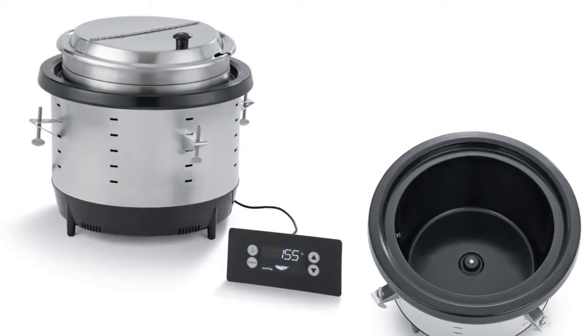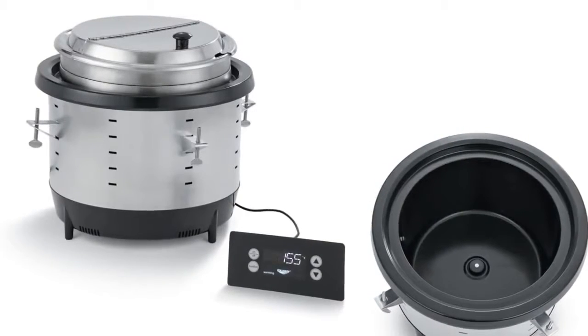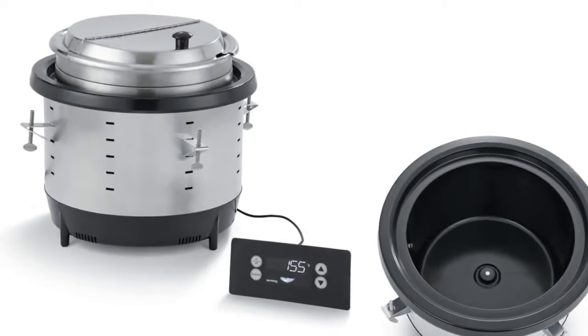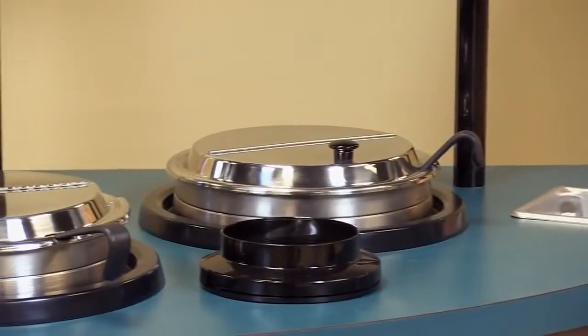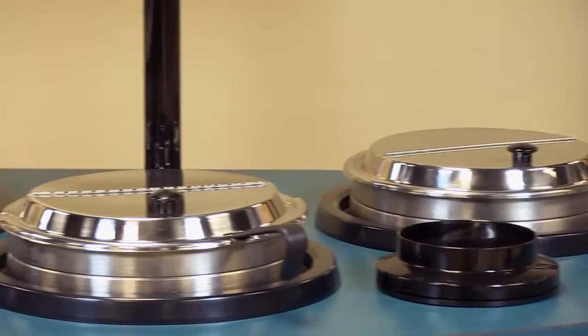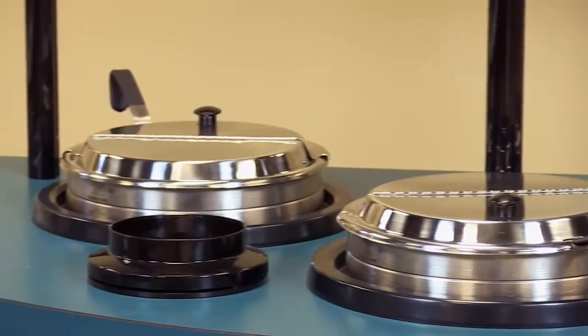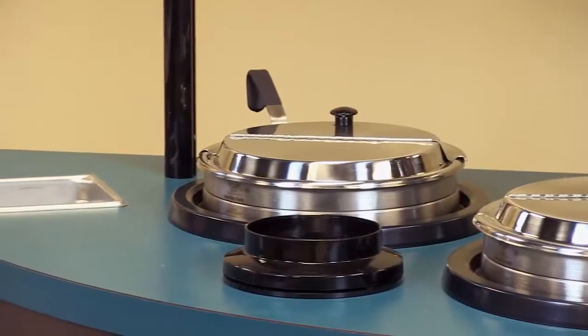Vollrath drop-ins use very little power. They come in a 250-watt warmer version or an 800-watt re-thermalizer version. The 250-watt unit is 120 volts and 2.1 amps, so you could put eight of these onto a 20-amp circuit.